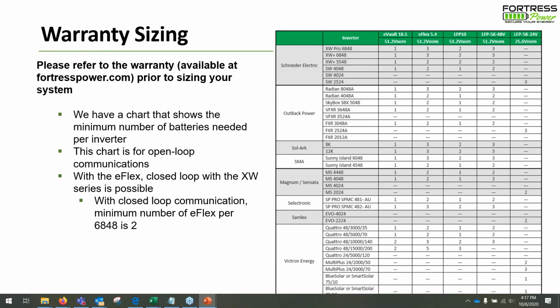And if you've seen the warranty letter, this is the sizing chart that we have here. The warranty is available on fortresspower.com. Please look at it prior to sizing your system. This chart will help, I think. This chart is the minimum number of batteries needed per inverter. Okay, and this chart is only for open loop communications.